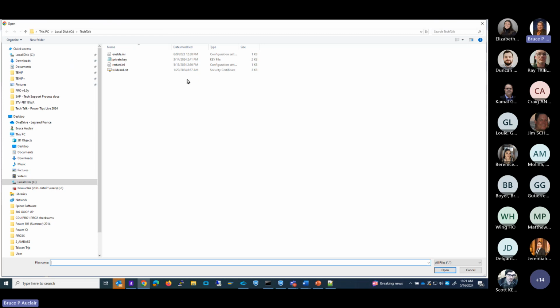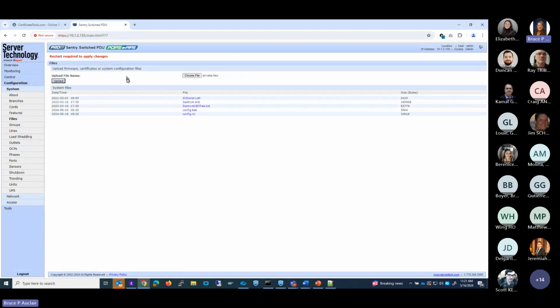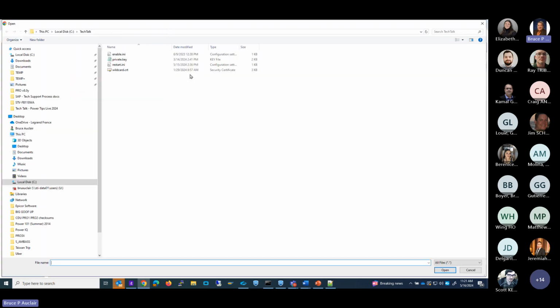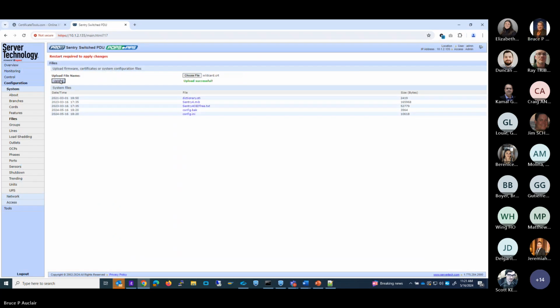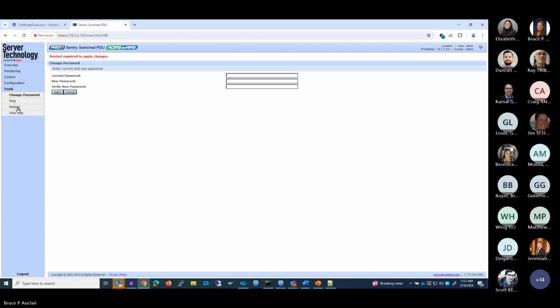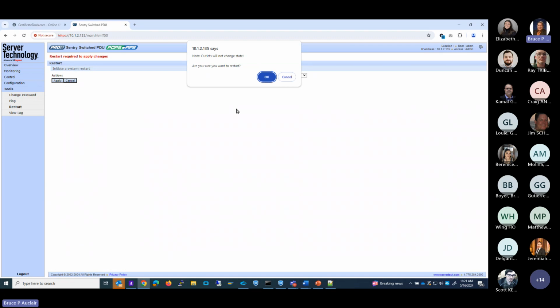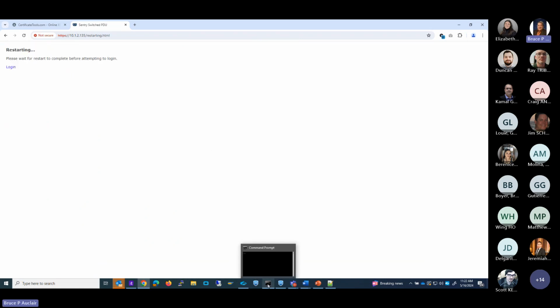So I'm going to choose the Choose File button. If you're using a different browser, it might say Browse instead of Choose File. And I'm going to upload the key file first. That's successful. I will proceed to upload next the wildcard certificate. Okay, so that is successful. We continue to see a message indicating restart is required, so that's the final step. Go to the tools, to the restart page. Use the drop-down list and choose the standard restart option. And as we'll see, this is just a soft restart. Outlet states, if it's a switched PDU, are not affected. And now it's a matter of waiting for the restart to complete.